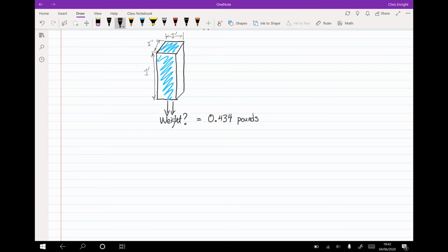For 1 foot of pressure head, so at 1 foot deep, or if you have to move water, hold water at 1 foot up, that's 0.434 pounds per square inch. So that's why we did 1 inch. So therefore, 1 foot elevation is going to be equal to 0.434 psi of either head loss or head gain. So we'll just call it that and not say it's plus or minus. We'll have to make that decision based on what the elevation of a given delivery point is.